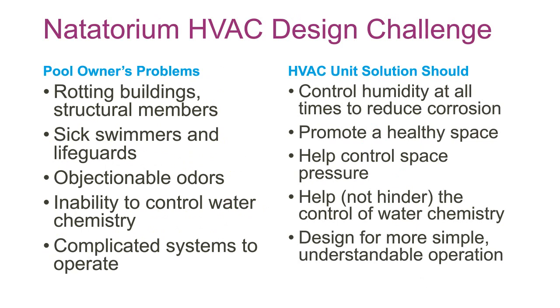And so when you looked at those design challenges, we were looking at it going, well, okay, you need to control the humidity all the time to reduce the corrosion. You certainly want to promote a healthy space. We saw that from the poll question, that a lot of you think the same way. You'd like to control the space pressure if you can to keep the humidity and chloramines from migrating into other spots. You prefer to be able to help the water chemistry rather than make its job harder. And you'd like to be able to design for a more simple system if possible. So those were some of the things that we were looking at when we got into the market.